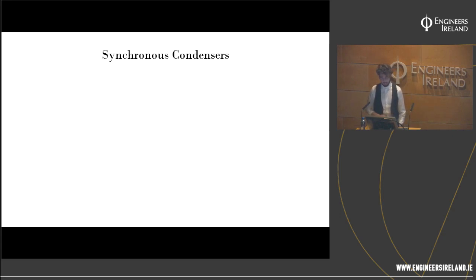Another alternative you could have is a synchronous condenser. What a synchronous condenser is, is a synchronous machine without a turbine. So it can't create energy. But what it can do, once synced to the grid, is provide voltage support and fault current. And inertia, because now, albeit less than a power plant because you don't have the turbine anymore, there's still the inertia of the synchronous machine once synced to the grid.